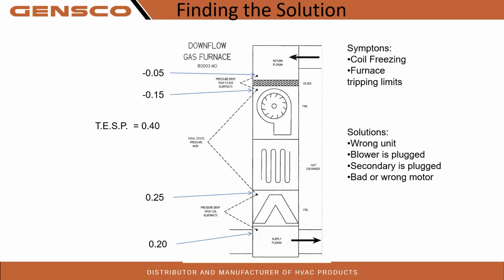So if you get a savvy homeowner, Boeing engineer, because I've dealt with a lot of those Boeing engineers, I know them, they're going to be reading through something and they understand a lot of it. So they think they want more air for some reason. They can tell it that it's actually a 5-ton furnace right now, when it's a 3-ton furnace. So if we do have airflow issues in those S8V2s and the TAM-X, first thing I'm going to do is probably check we have the correct model number in there. Check in the app or through the CDA, the 7-segment display on the circuit board.